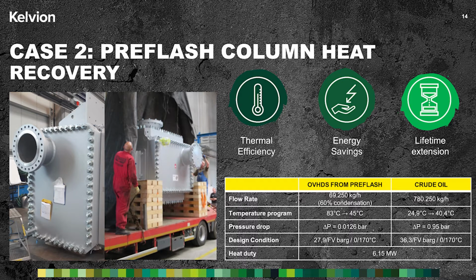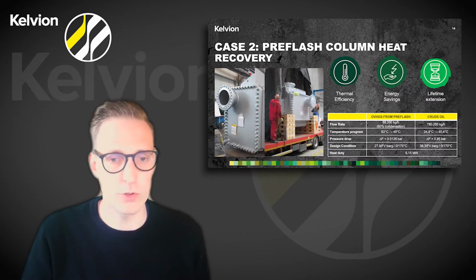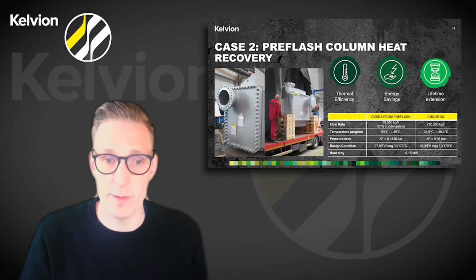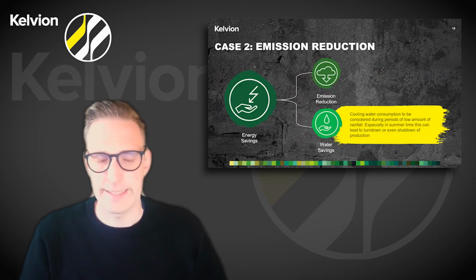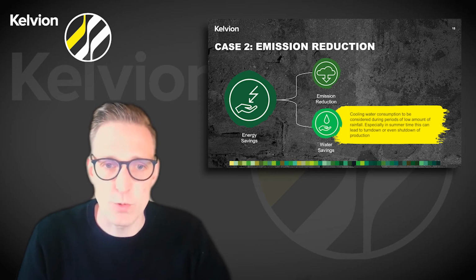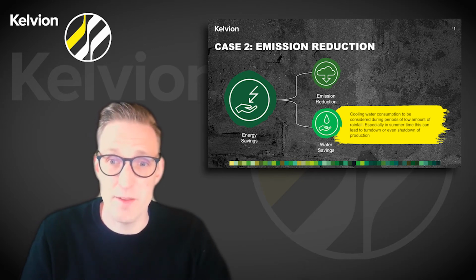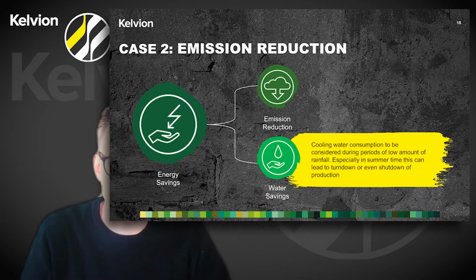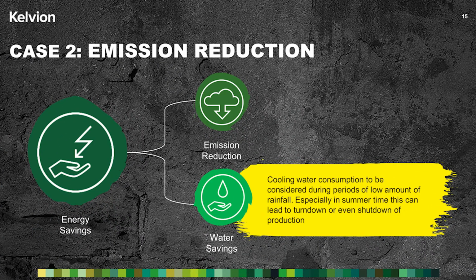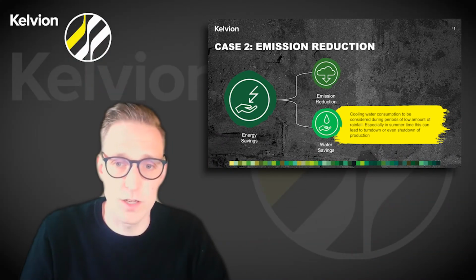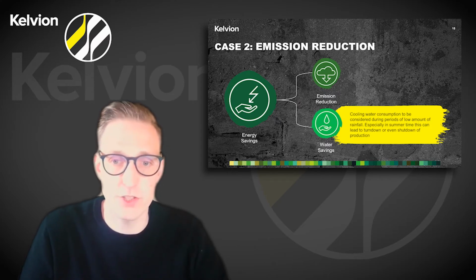In this application, overheads from the pre-flash column are used to preheat the crude oil. Again, this is a high-duty heat recovery application for the K-block. And did you know, an interchanger that mainly is used to avoid the usage of primary energy also has another important and valid advantage nowadays. Every single recovered kilowatt reduces the amount of cooling as well. This results in lower power consumption for air cooler fans, for example, or in the reduction of cooling water. Periods of low rainfall bear the risk that rivers may have too high a temperature to cool properly, or the volume is too low to cool down as required. This makes additional air coolers or cooling towers necessary to avoid turndowns or even shutdowns of production.